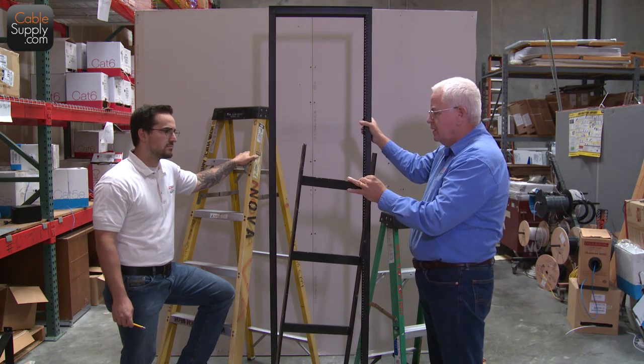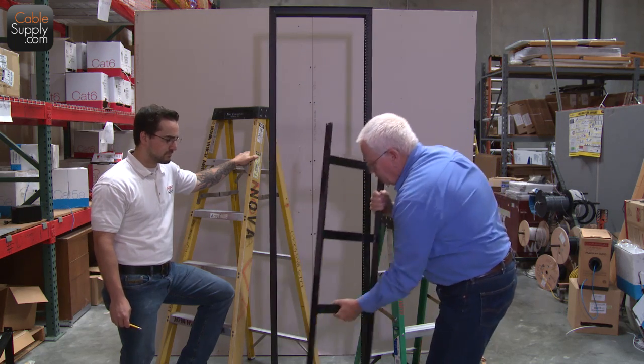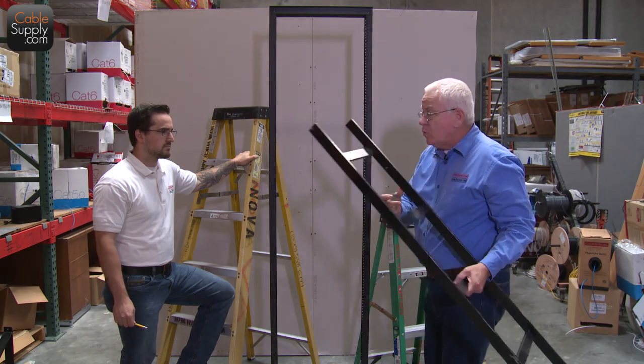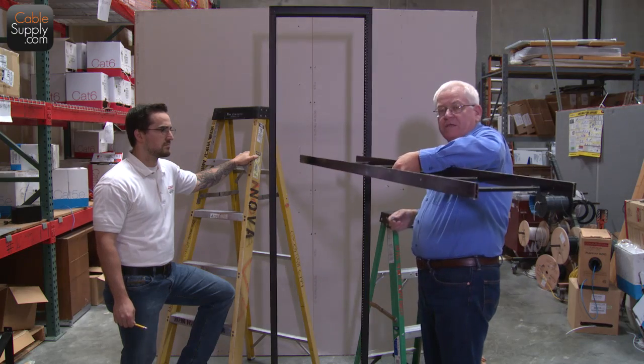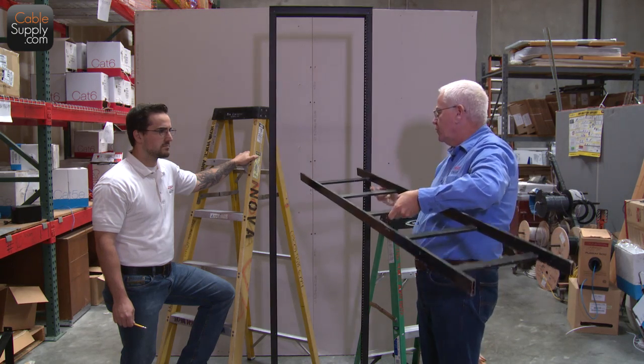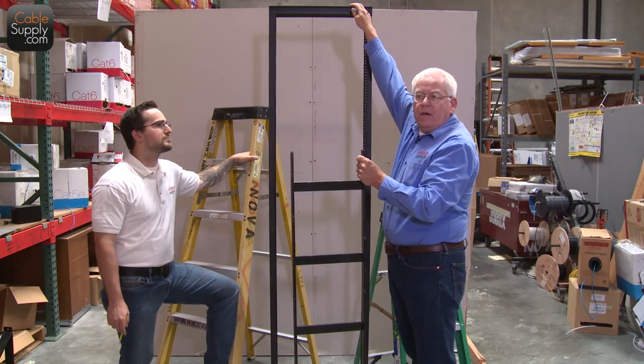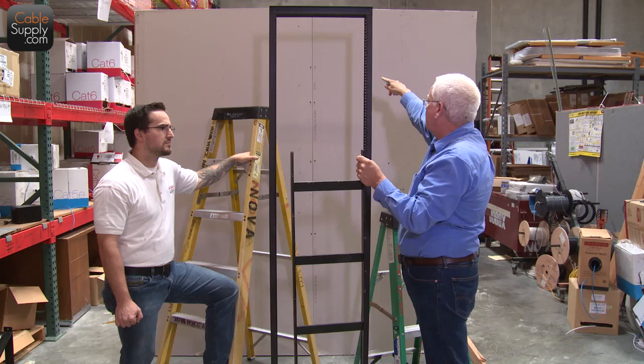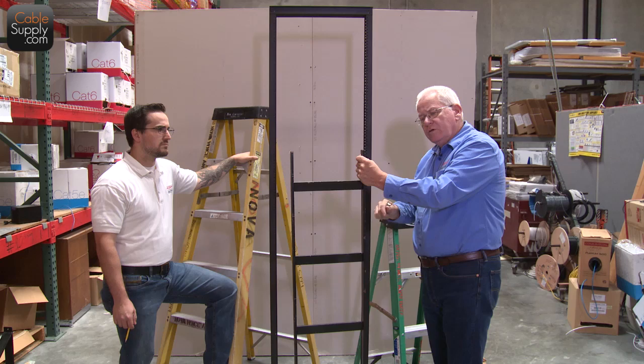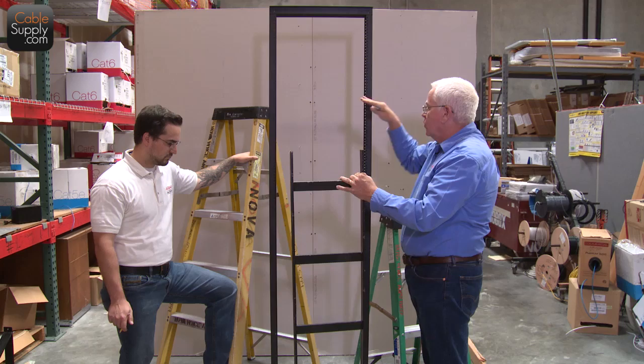The cable ladder also adds stability to your data rack — you can see it wiggles a little bit, but when we're done it won't be doing that. There are many ways to do this positioning. One way is to just lay it up there and mark underneath, or you can use a level. I recommend a level of some sort. You can also measure from the floor to the top of the L-bracket and then make a line on your wall at that same distance from the floor. Today we're going to use a level to find where to put the bracket on the wall.